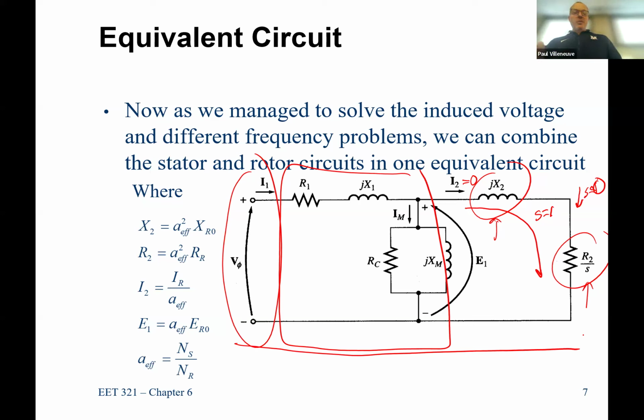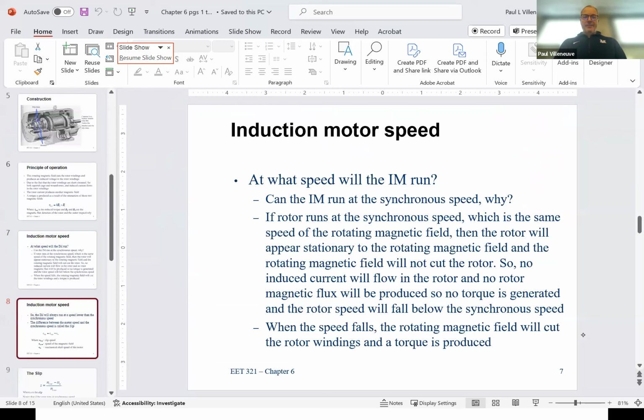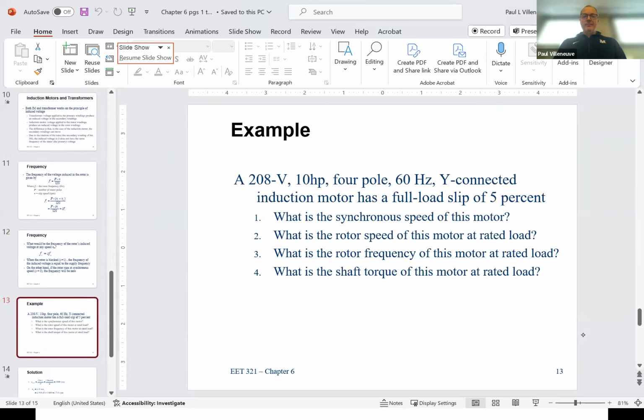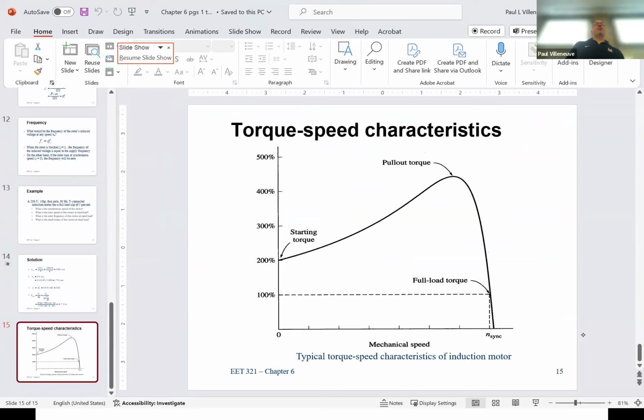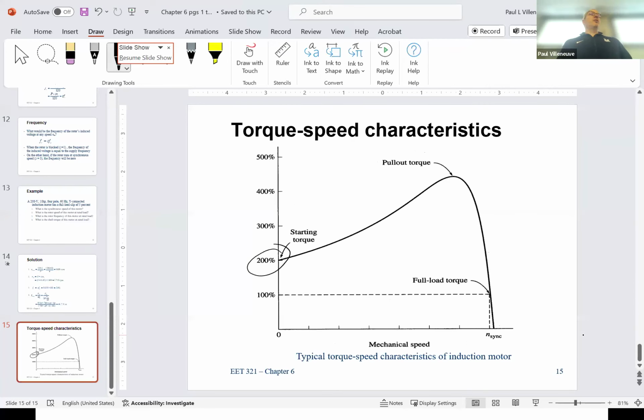Over here, as we talked about when we looked at this curve here, induction machines can operate at essentially any speed. They can operate at no speed, or they can operate at 100% speed or synchronous speed. And as long as the machine is kept cool, you certainly could run that at 200% of its full load torque, but the likelihood of the machine lasting a long period of time is not going to be very good, right? Because the full load torque is down over here.